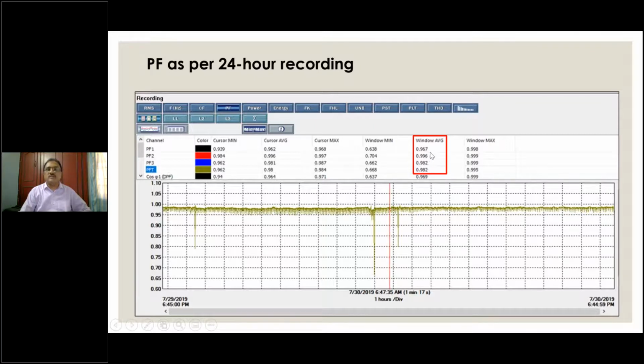So normally what happens is many industries and facilities connect single phase loads indiscriminately. So they may have connected a lot of single phase loads to the R phase only, because it must be the first phase that is available, easily accessible in the panels. So at various levels in the panels, single phase loads would have been added. We have advised them to take a look at the overall facility and redistribute in such a way that the average power factor is not unbalanced like this. This unbalance will lead to unbalance in current, and therefore the suggestion.